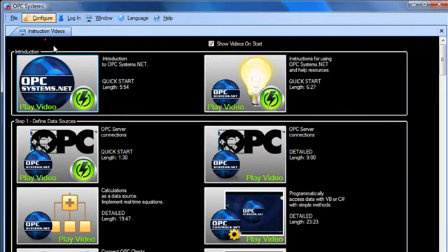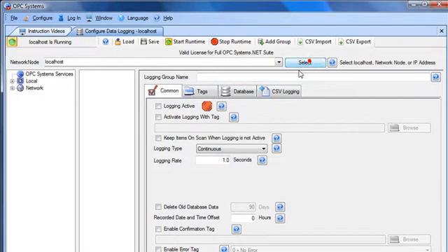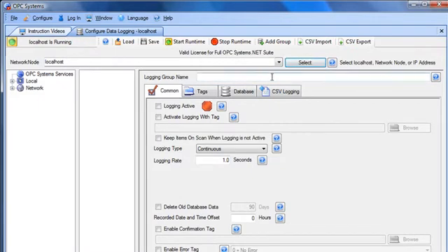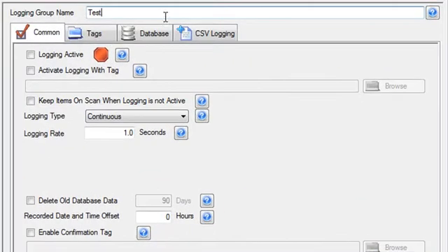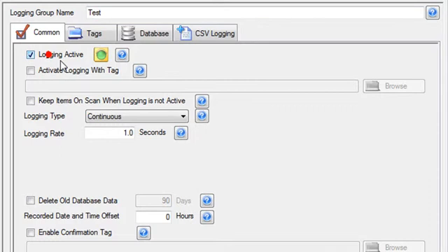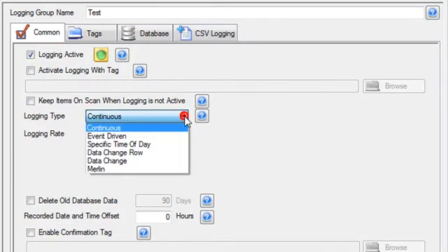I'm going to set up a data logging group under configure data logging. I'll select the service that I want to configure. Enter a logging group name and make the logging active. I'm going to use the continuous type, but the buffering will work with all of the types, whether it be event driven, specific time of day, data change wide table format, or narrow table format.